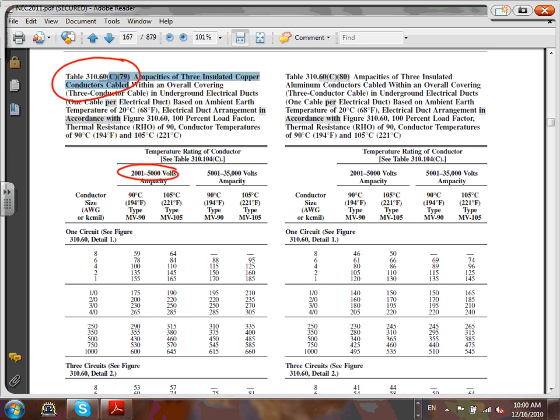It's the 90-degree column. That's weird, because now they size a medium voltage cable based on 90 degrees. We never do that on low voltage. On medium voltage, we size based on 90 degrees. So here's my 90 degree medium voltage cable. And what was the amp? 260. So I need 260 under 90 degrees. Is that 4 aught? Right here. Can you guys see that? 4 aught. Is that what I came up with here? 4 aught.